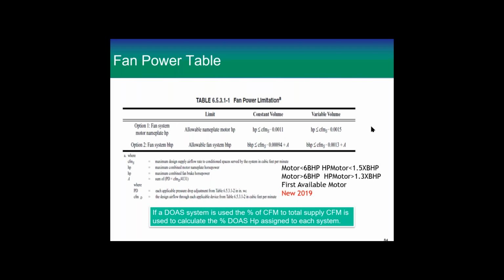Now, you do this every time because it's easy to do, and if you pass, you pass, and you're through. Now, if you didn't pass, you go down here and you run your brake horsepower. Your brake horsepower, you'll have to get from the manufacturer or whatever for the piece of equipment. Your brake horsepower is less than or equal to, this one is 0.0013 times the same CFM, plus A. Now, what is A?